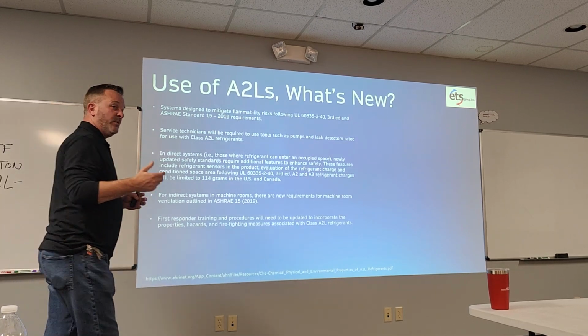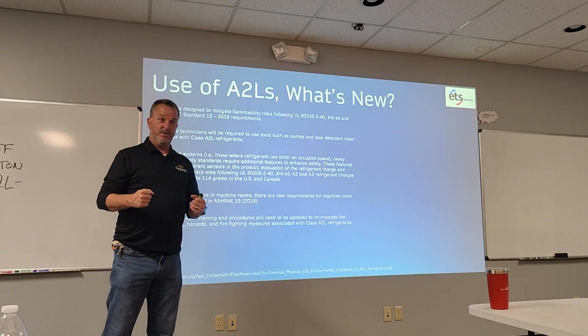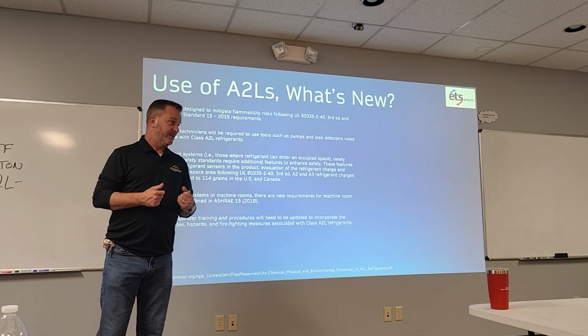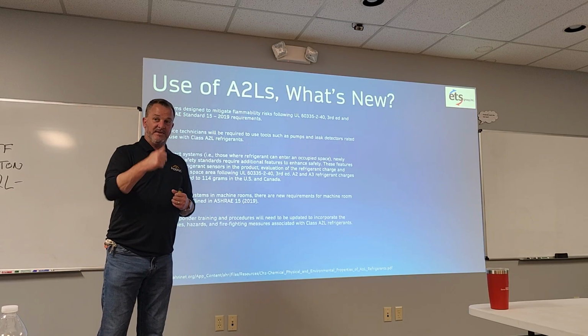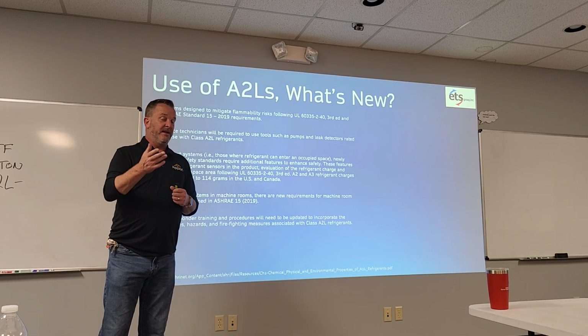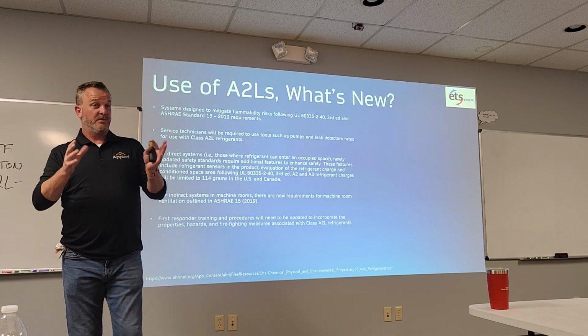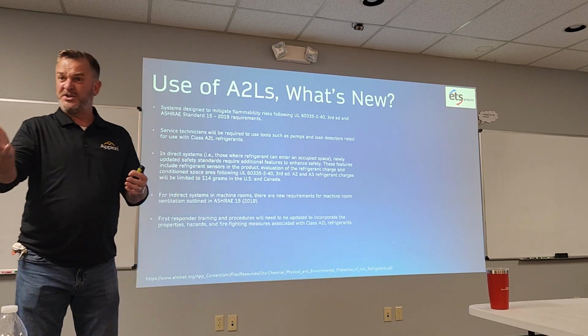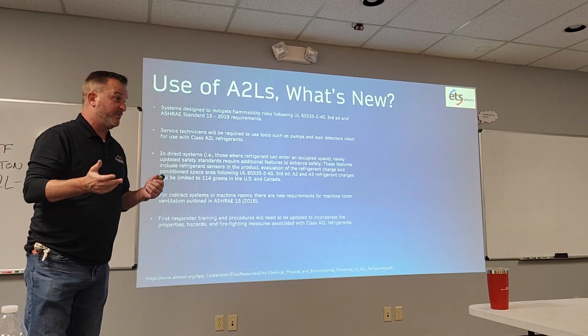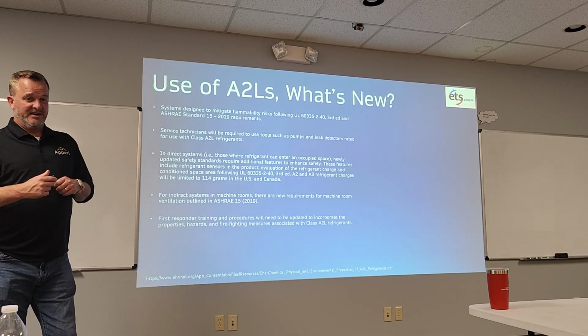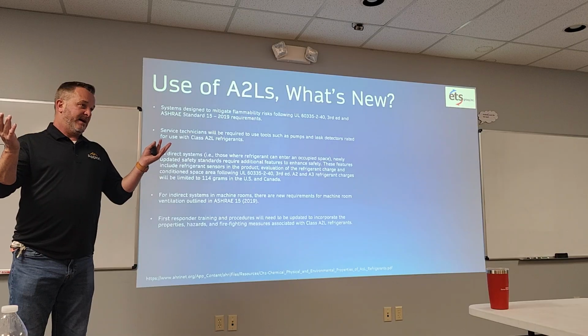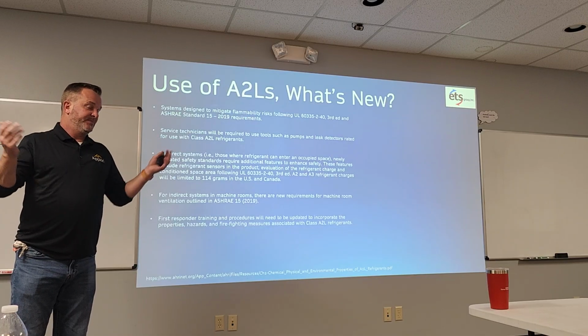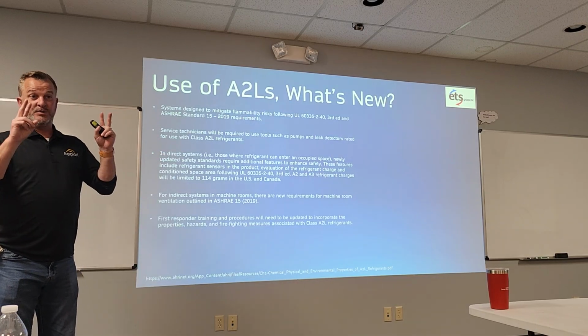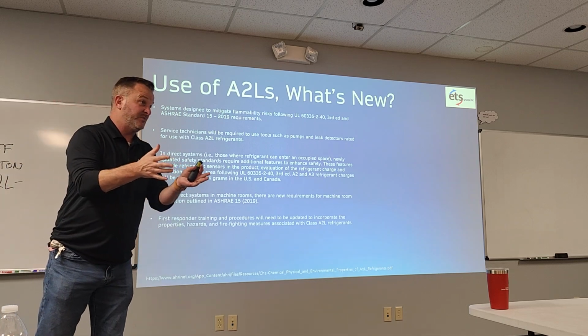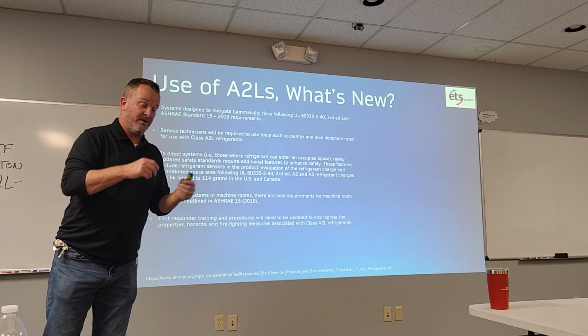In this True video, he takes the compressor out, and to recover it he just snips the line and cuts it. At this appliance place, they deal with this a lot with mini fridges, and now window shakers and window units are going to have A3 refrigerants, propane and butane. So he just snips the line, because you don't have to worry about it hurting the atmosphere, it's zero GWP. The only time you'd want to technically recover it is if you're in an enclosed space and don't want that stuff leaking out while you're in there.